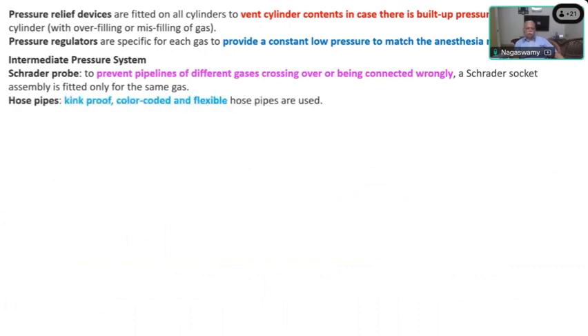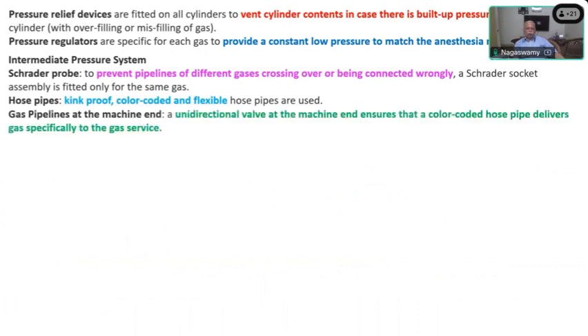The hose pipes are kink proof, color coded and flexible. Gas pipelines at the machine end are connected with a unidirectional valve so that there is no reverse flow, and they are color coded and matched with a specific gas service. There are pipeline pressure indicators as well as cylinder pressure indicators in the modern anesthesia workstation. Whereas in the earlier anesthesia machine, the pressure gauge will show only the gas cylinder pressure. There is no indicator for the central pipeline pressure if it is connected to the older machine. All of you will be aware, because most of you are now using only workstations in the majority of hospitals, the panel displays both the cylinder pressure as well as the central pipeline pressure, which is again a safety measure incorporated in the workstations.